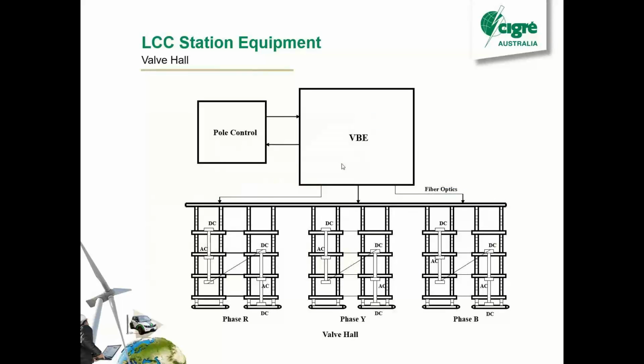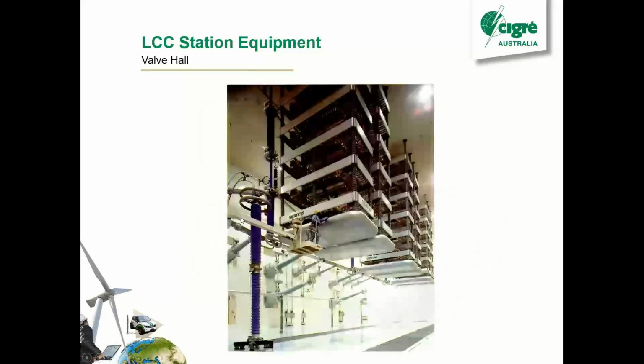This is showing basically how the firing pulses get in. We have part of the controls called the pole control, which decides the firing angle. That then tells the VBE to send the pulses. This stands for valve-based electronics, and the valve-based electronics has fiber optics. This is all in the control room here, and then you've got fiber optics from the control room out onto the thyristor stacks to each thyristor. If you've got the electrically triggered, these fiber optics have to go into a little box for each thyristor, which converts the fiber pulse into an electric pulse. But for the light triggered, you can go straight from the VBE into the thyristors, so you can see how you're improving the reliability a little bit there. It's showing you the complete converter there.